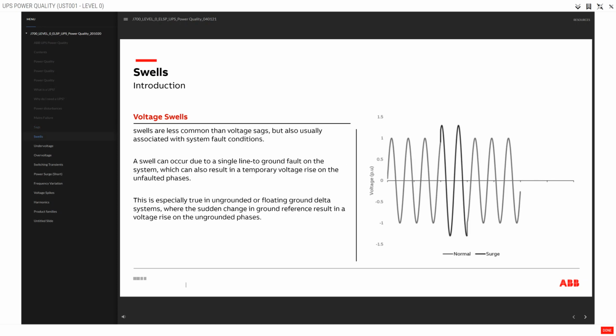Voltage swells. Swells are less common than voltage sags, but also usually associated with system fault conditions. A swell can occur due to a single line to ground fault on the system, which can also result in a temporary voltage rise on the unfaulted phases. This is especially true in ungrounded or floating ground delta systems, where the sudden change in ground reference results in a voltage rise on the ungrounded phases.